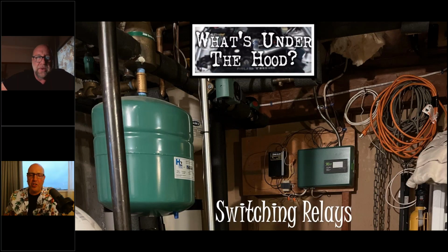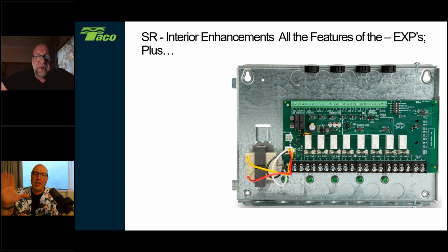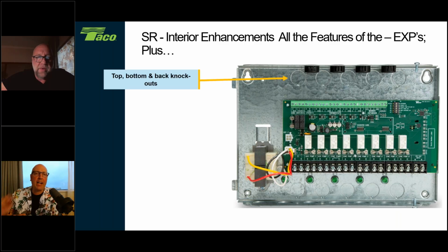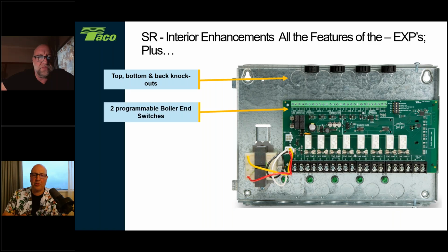What did we do different under the hood on switching relays here? So like I said, this is just like our EXP, the Dash 4 EXPs, but here's some of the few changes that we did. We added back knockouts. So those of you that don't want to have the wires coming out of the top and bottom of the control board, we added a back knockout so you can run those wires through the wall. All right, piece of plywood, something like that. So that's a change that we've done. And we were able to do that because the circuit board got smaller, and we increased the outside dimensions of the controller about a 1/4 inch all the way around. So not a huge change in size, but we got that circuit board smaller so we can allow for the back knockouts. We still have those same programmable end switches, the boiler and priority, but they're programmable, and I'll show you what that means in a bit.